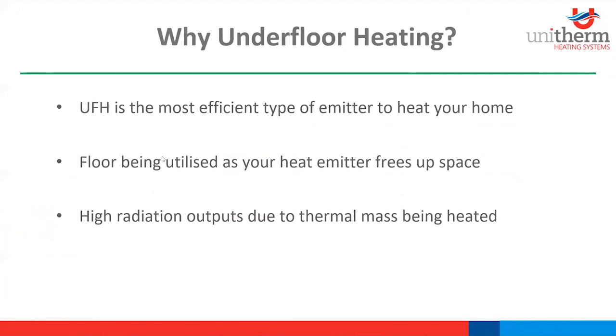Why go with underfloor heating then? Underfloor heating is probably the most efficient type of emitter to heat your home. As the floor is your emitter, instead of traditional emitters such as radiators, you now have a much larger area. So instead of a small radiator with a high flow temperature, you can go with a bigger area and a lower flow temperature. Obviously, the lower the flow temperature, the higher the efficiency of the heat pump and the lower the running costs. Also, the thicker the screed for the underfloor, the more thermal mass it will have and the more radiation it will produce. So high radiation outputs there, due to the thermal mass being heated.